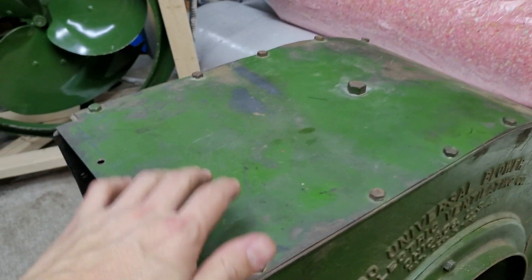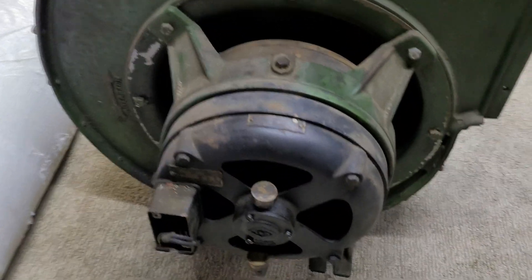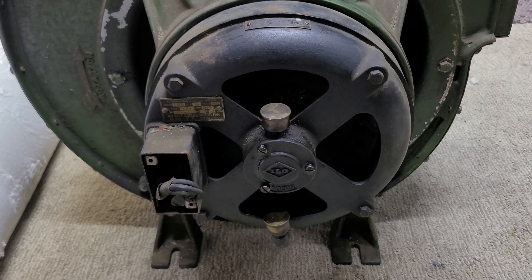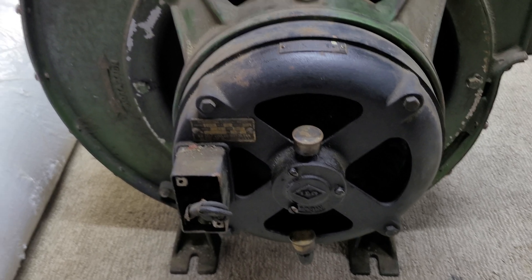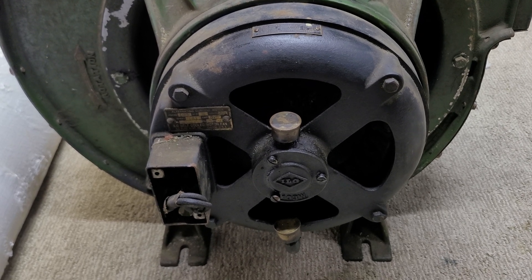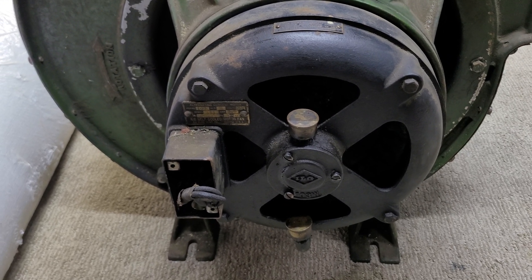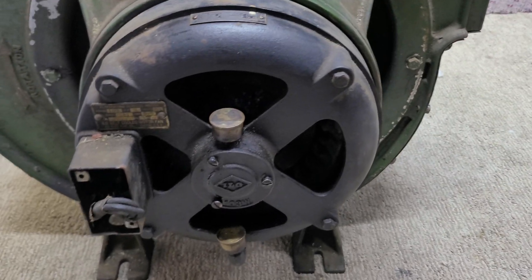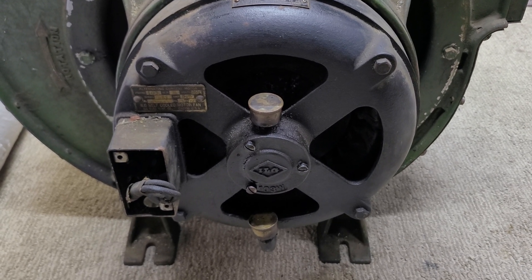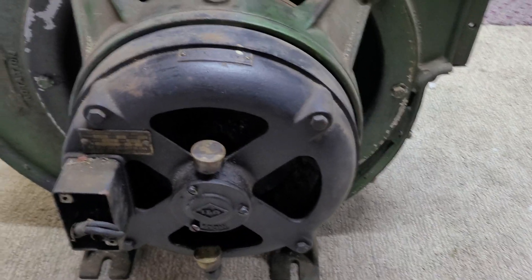The sides of these are cast iron, and this is sheet metal steel, but it's pretty thick steel. This one is a 7/8 horsepower, about 12 inches in diameter, so it's quite large. This particular one was offered with three different size motors and three different RPMs. This is the slowest RPM for this fan. They also had an 855 and an 1140 RPM motor, which consecutively got to higher horsepower — I think the next one was like a horse and a half and then a four horsepower. I can't even imagine the motors on those.